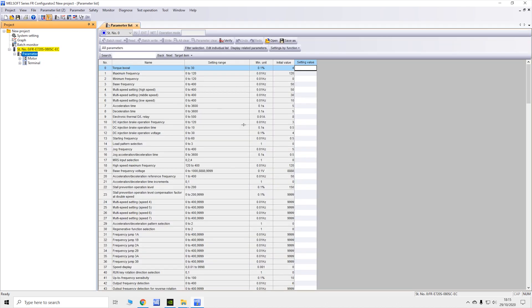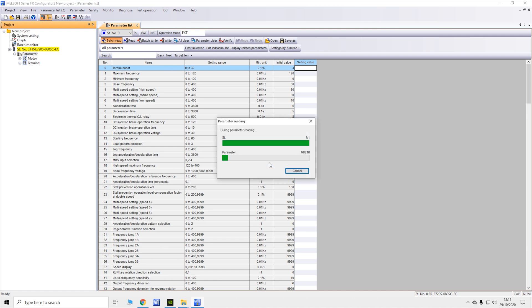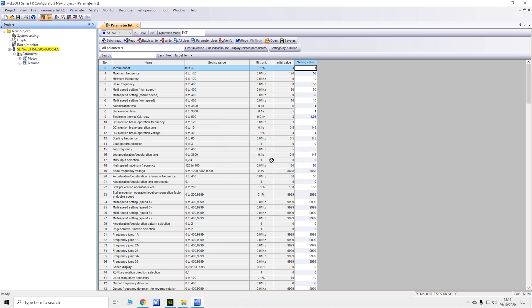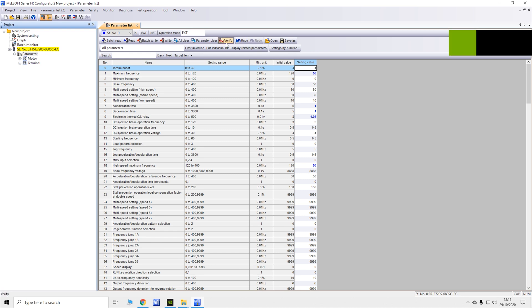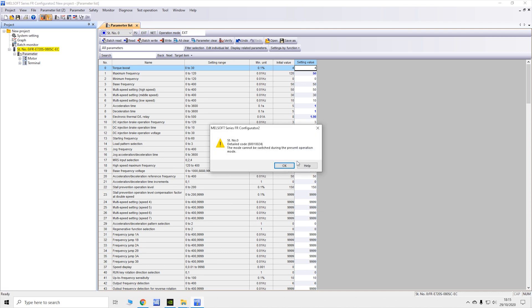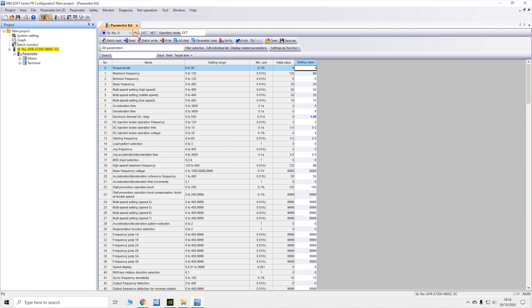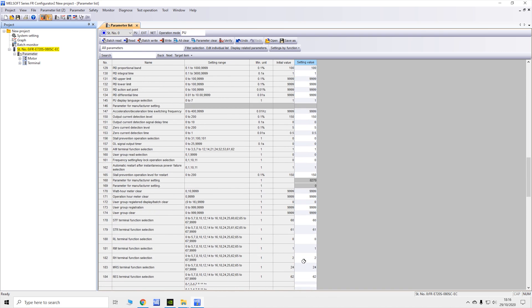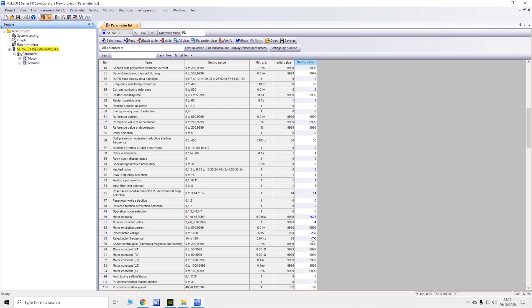Now you can open up and see all your parameters — the defaults are displayed. Click the Connect button in the small window at the bottom and you are now connected. You can see the connect status up at the top. Now do a Batch Read to read all the parameters that are inside the drive. You also have a small control panel where you can select between PU, external, and other modes. Down in the parameter list you can see all the parameters currently inside the drive.